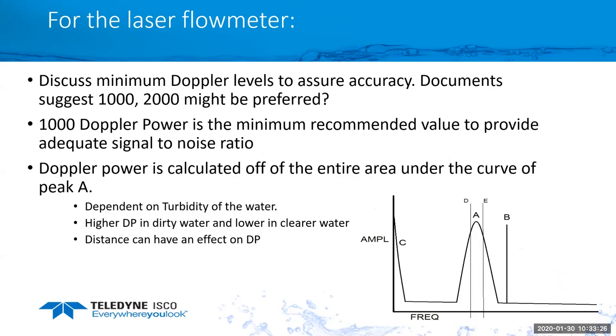The other question was to discuss the minimum Dopplers to assure accuracy. By default, the equipment is set to 1,000 for minimum Doppler. What that does is it provides an adequate signal to noise ratio to make sure we're getting a good return signal. As you can see with that graph on the bottom right, the Doppler power is calculated off the entire area underneath that curve. You see that curve A, that is built by the 5,000 spectral readings that are taken when the laser's on for 2 seconds.